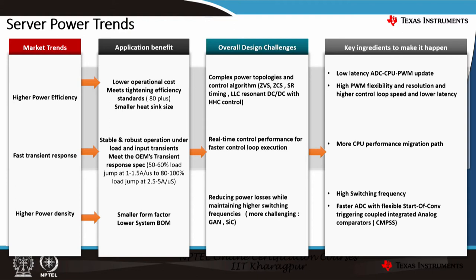Moving on to server power trends — the market trends demand higher power efficiency, fast transient response, and higher power density. Higher power efficiency provides lower operation costs, meets tightening efficiency standards (greater than 80%), and results in lower power loss, meaning a smaller heat sink is needed. Fast transient response enables stable and robust operation under load as well as input transients, and meets OEM transient response specs. Higher power density delivers a smaller form factor with a lower system BOM.